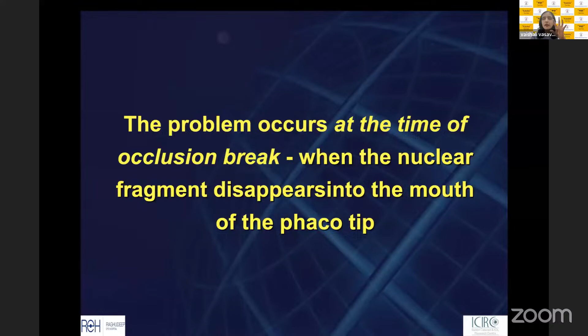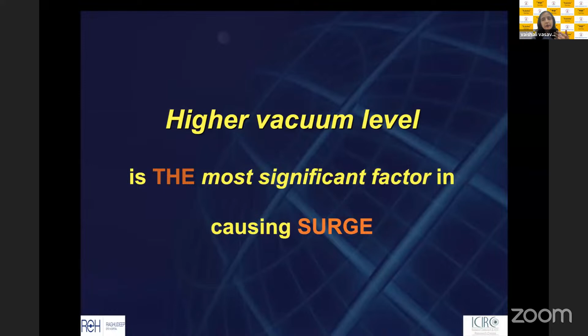Now, as soon as you break the occlusion, the vacuum inside the tubing is still at 500. So it will suck according to the preset vacuum and try to bring in that much amount of fluid. Therefore, we need to understand that the most important factor in creating a surge is not your flow rate, not your bottle height, but your preset vacuum. Even if I have a high flow rate or a low flow rate, if my vacuum is extremely high, I am very likely to have surge. So the vacuum primarily decides.